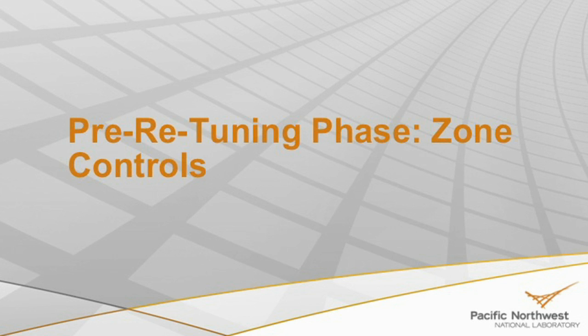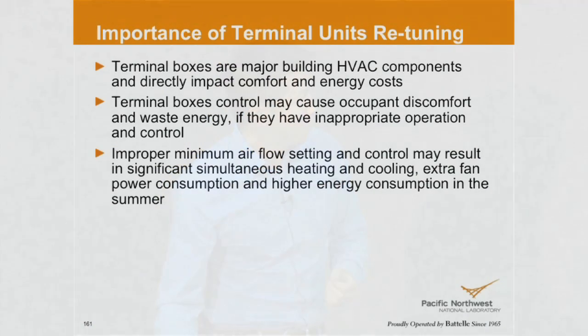In this section we want to talk about the terminal box control. So the terminal box is the setup of the duct and the damper with automatic control to provide thermal comfort and ventilation to thermal zones. The thermal comfort is provided by the thermostat, which controls the temperature set point for the zone. And the ventilation requirements are met by the minimum airflow set point for the terminal box. So here we can give more information about this.